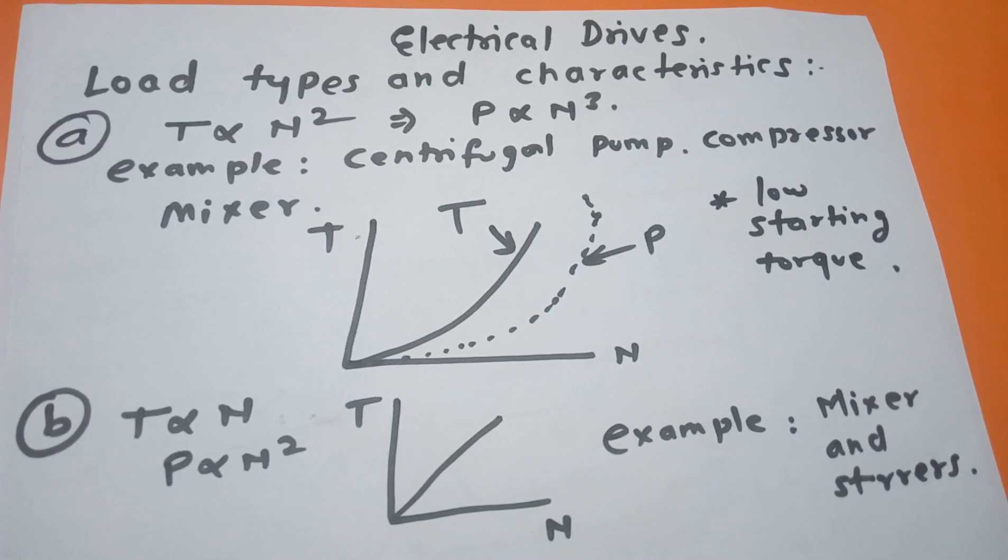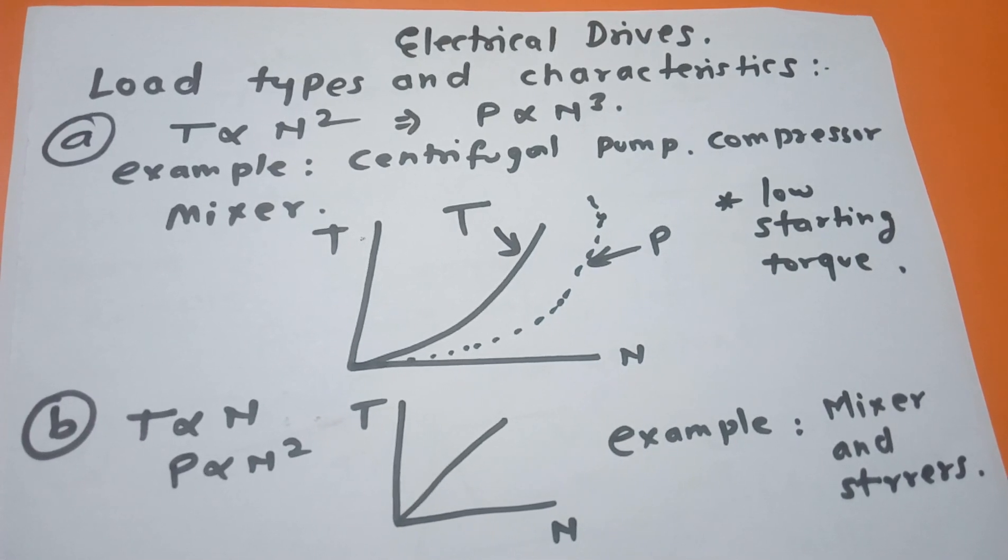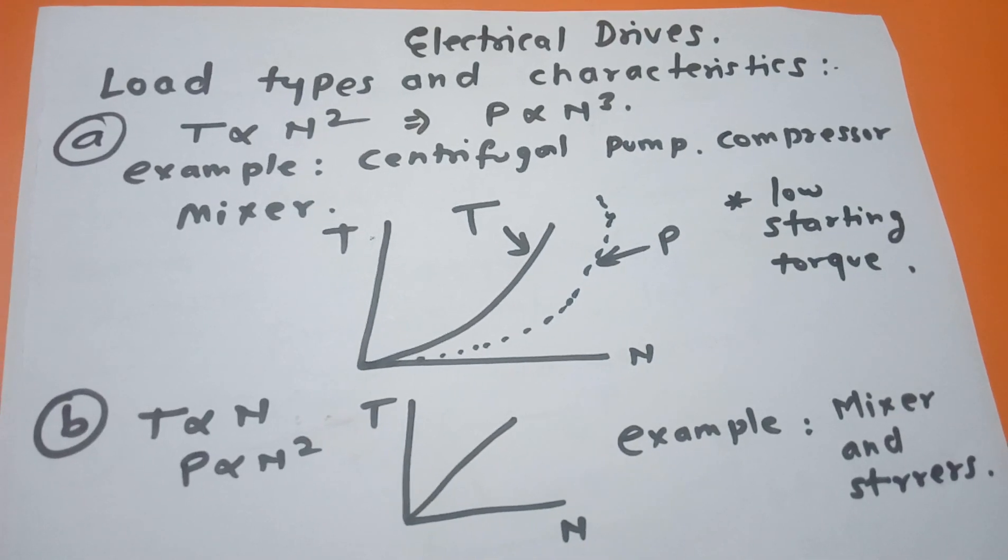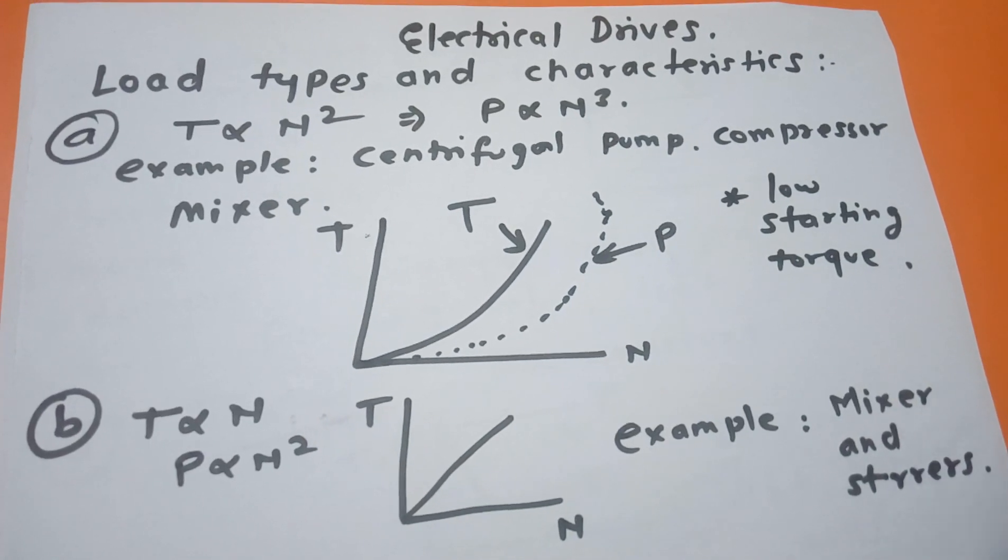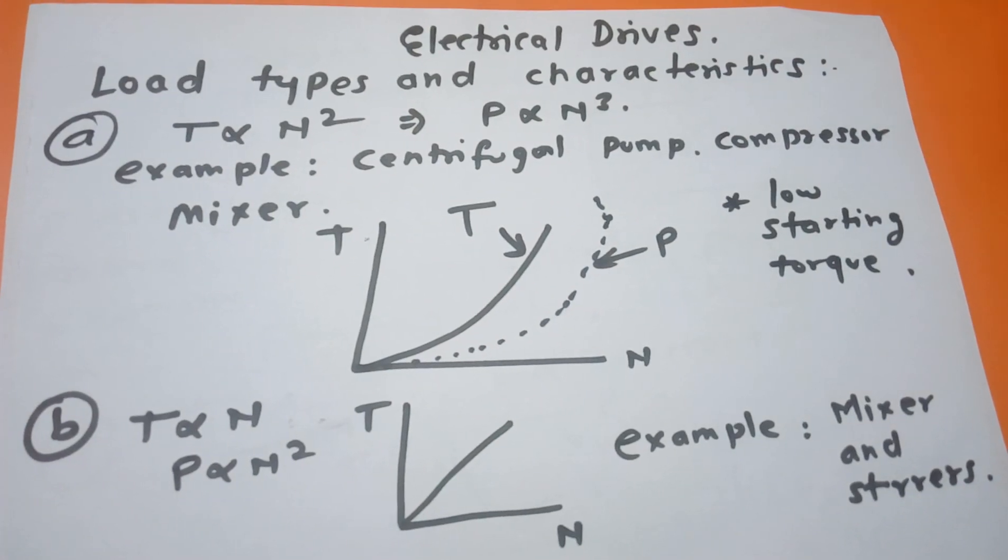For that purpose, the load type characteristics are very important. The first is the torque is proportional to speed square. This is called parabolic characteristic. In this case, power is also proportional to speed cube.